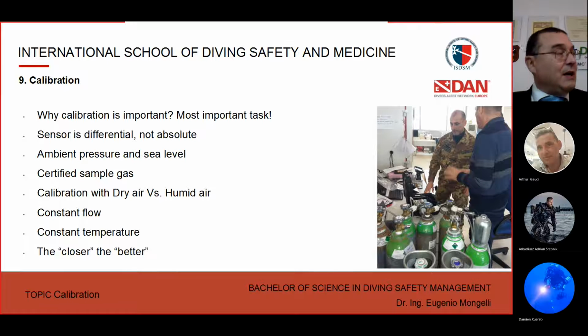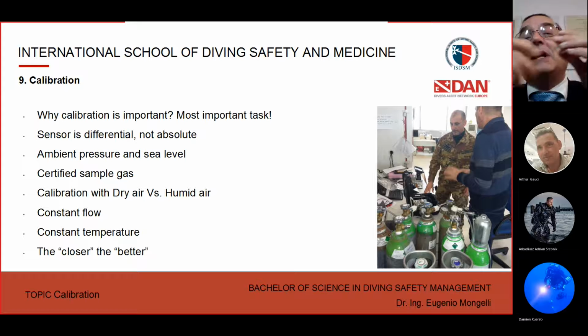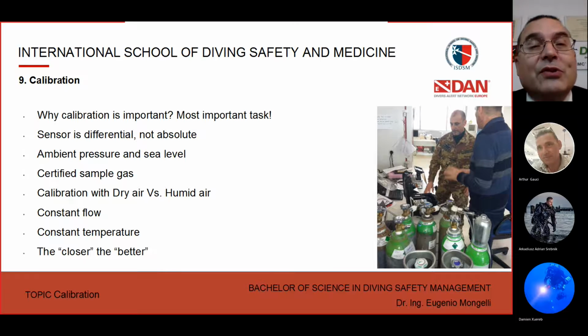Just for giving you an example, if I have an oxygen analyzer reading 21%, I calibrate in air, okay? Then I put the same analyzer inside a hyperbaric chamber, okay? And always with air, I don't put any kind of oxygen, helium, nothing, just air. And then I go down 10 meters, okay, meaning I double the pressure, so I go to 2 bar of absolute pressure. The analyzer, if it's well calibrated, if it works well, will show you 42%, so double of 21. But the concentration is always air, you understand? But the partial pressure is double, and it means that from 21 you go to 42. Understand? So this is extremely important.